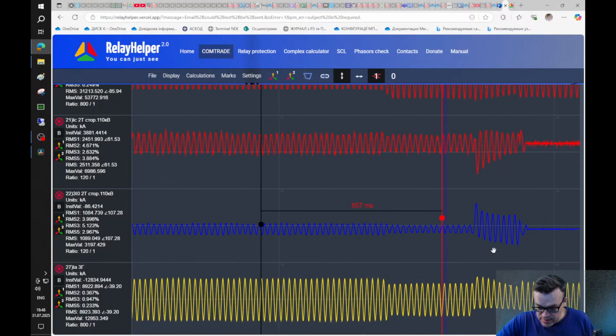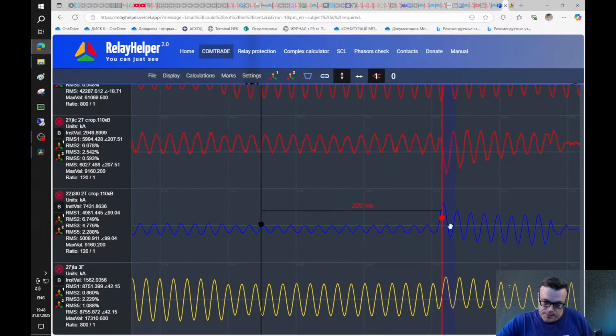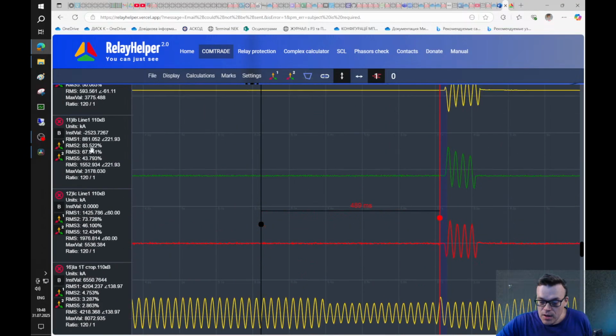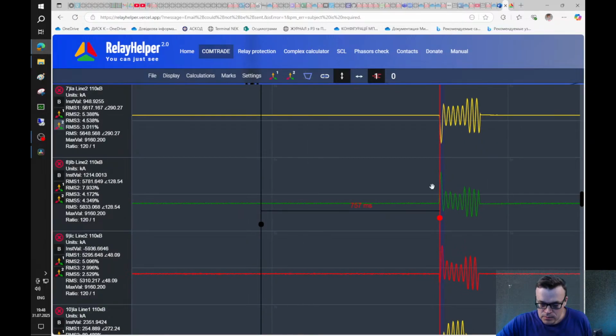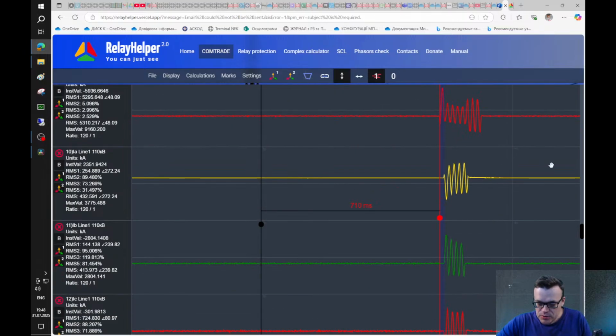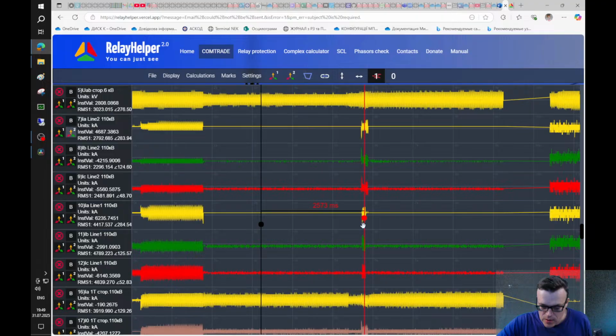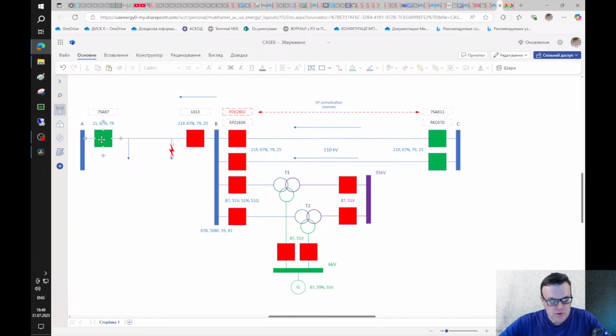And what do we see next? We see a bounce of currents, and I want to describe why it happens. A little bit about the protections on that side. At this point only these protections had operated, and I want to remind you that from the substation A side we don't have automatic reclosing, because there is no voltage transformer on the line and we can't implement synchro check. So during generation of this power plant, automatic reclosing is disabled.